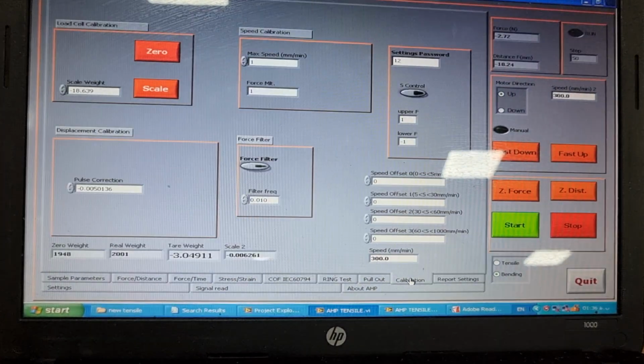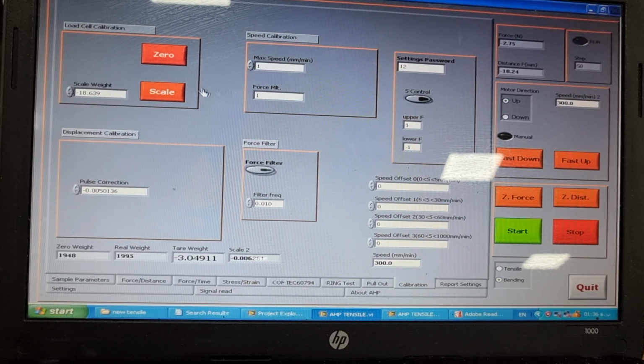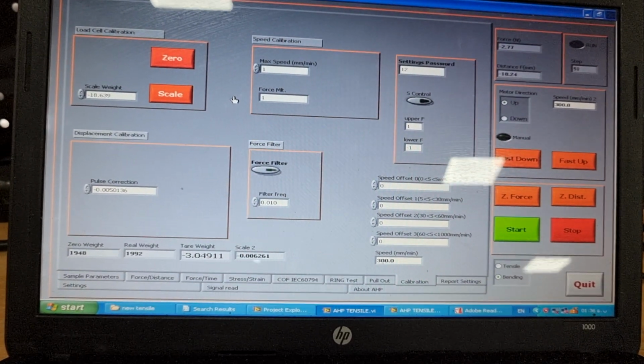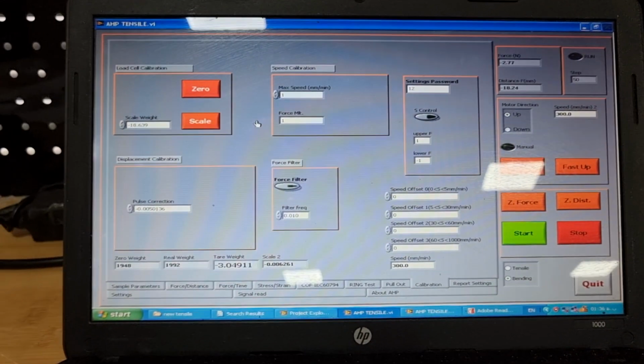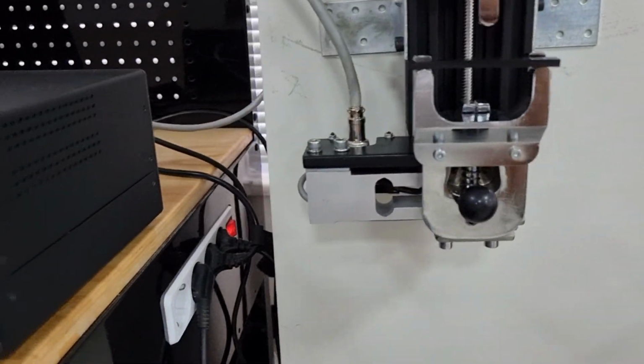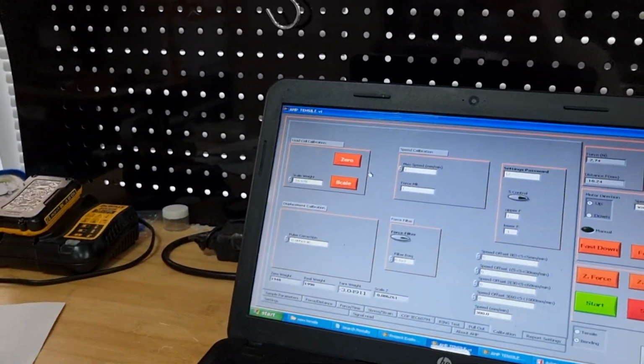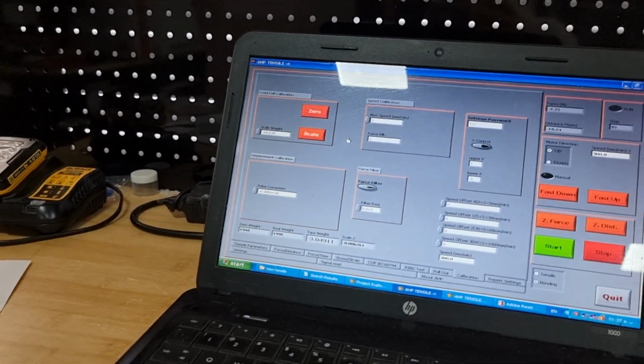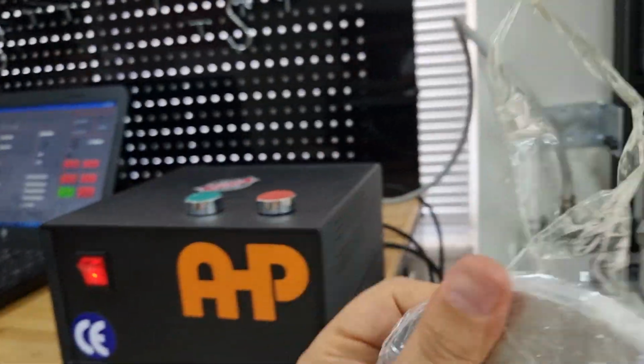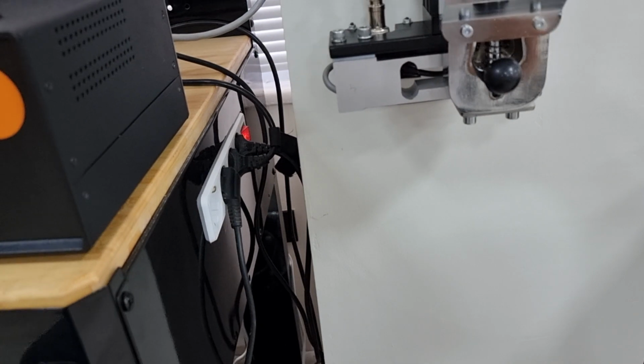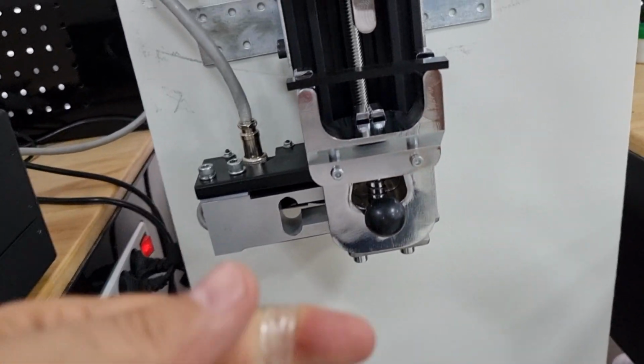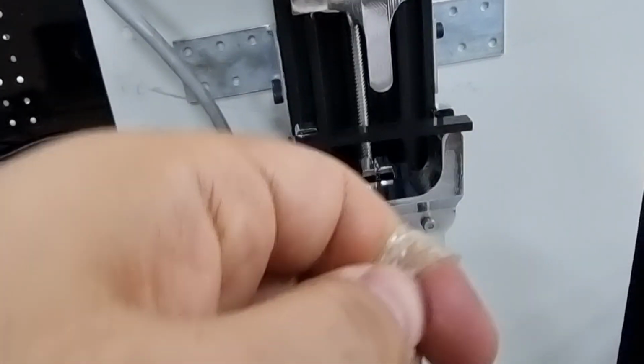First of all, I'm going to show you how to calibrate it. The calibration procedure is very easy. When it's in this mode like this, the load cell is here. With no force, you need to click on 0. And with a definite force, for example, this is 1.9 kg, a definite force that you will hang here, for example, from these points.